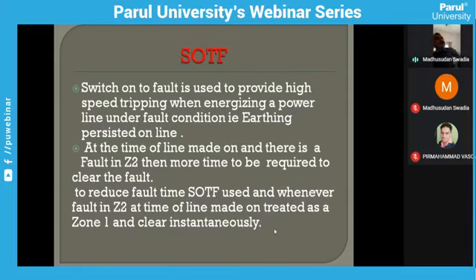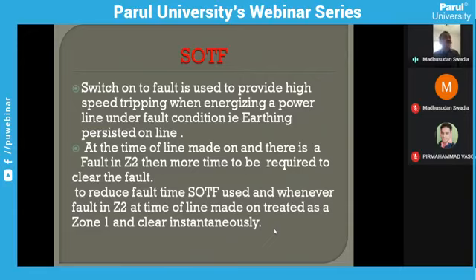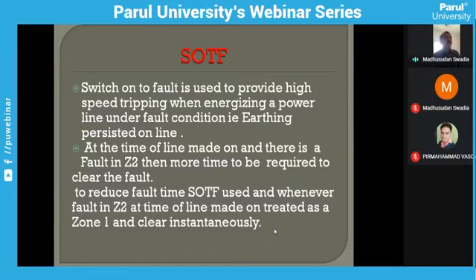SOTF — Switch On To Fault — is also an important feature. Sometimes during maintenance, an earthing may remain pending on the isolator or any phase may be earthed inadvertently. If we try to switch on the line under that condition, SOTF will immediately trip the line without any time delay — its reach extends up to Zone 2. Switch On To Fault is used to provide high-speed tripping when energizing a power line under fault conditions, such as when earthing is persistent on the line at the time of switching on.